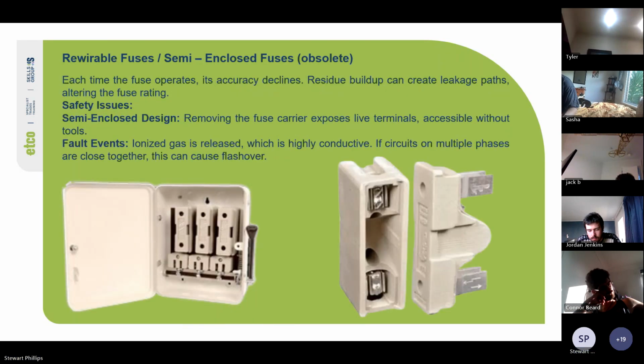Cool. And then you've got rewirable fuses, semi-enclosed, so that yeah, each time the fuse operates, its accuracy declines. Residue buildup can create leakage paths, altering the fuse rating. And safety issues, the semi-enclosed design. Removing the fuse carrier exposes live terminals accessible without tools. And in fault events, ionized gas is released, which is highly conductive. If circuits on multiple phases are close together, this can cause a flashover event.